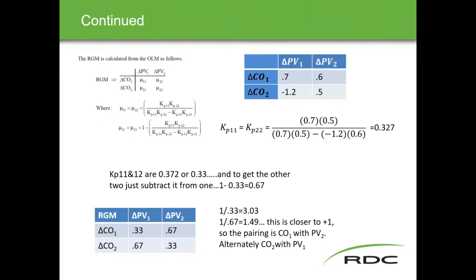If you say what pairing are you going to pick, you pick the pairing with the highest numbers — in this case controller one with PV2 or controller two with PV1. So controller one will control PV2 and controller two will control PV1. This is still just measuring the level of interaction. From here we get into the transfer functions for the loops and applying all the stuff inside the controller related to the decoupler — lead time, lag time, and all that.